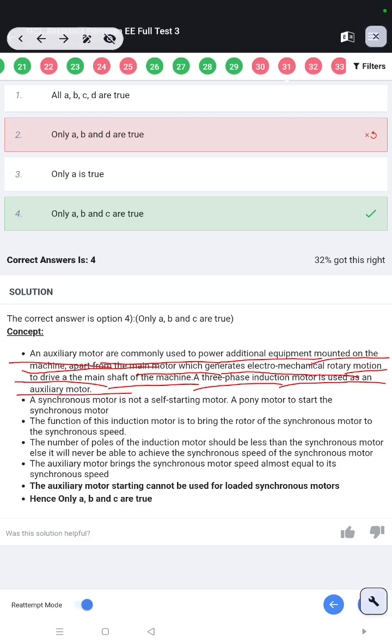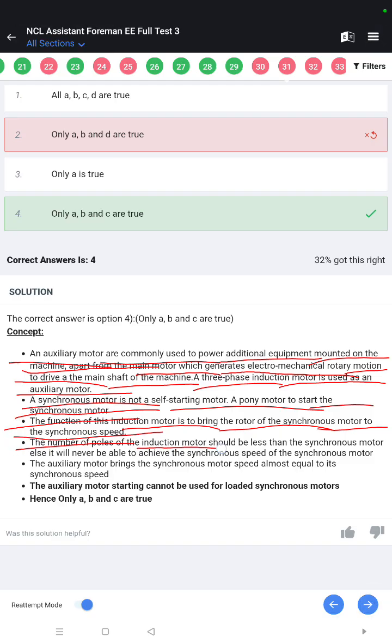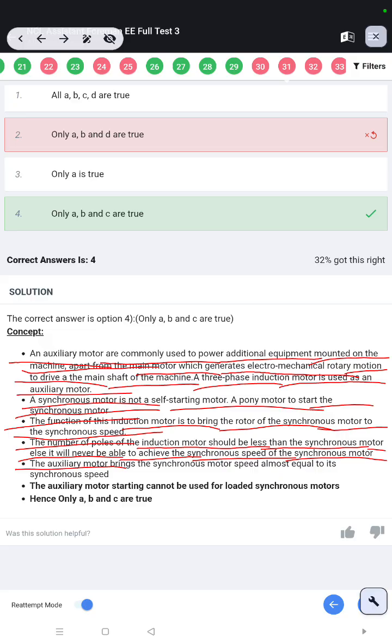A synchronous motor is not a self-starting motor, so a pony motor is used to start the synchronous motor. The function of this induction motor is to bring the rotor of the synchronous motor to the synchronous speed. The number of poles of the induction motor should be less than the synchronous motor, else it will never be able to achieve the synchronous speed of the synchronous motor. The auxiliary motor brings the synchronous motor speed almost equal to its synchronous speed. The auxiliary motor starting cannot be used for a loaded synchronous motor, hence only A, B, C are true.